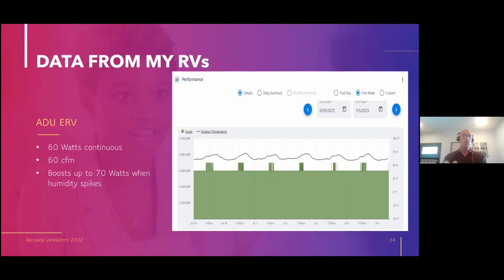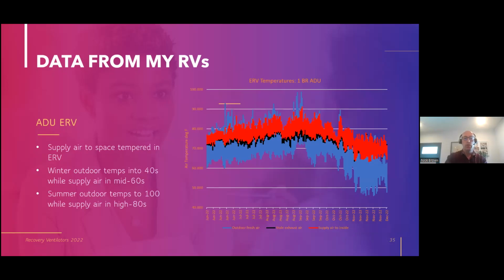This ERV runs at 60 CFM, 60 watts. That's not especially efficient. It's not an ECM efficient motor situation like some of the best in class systems, which can get down more like 0.6, 0.5 watts per CFM. This is operating at 1 watt per CFM, so it's not by any means a best in class unit. So I wanted to show you that.